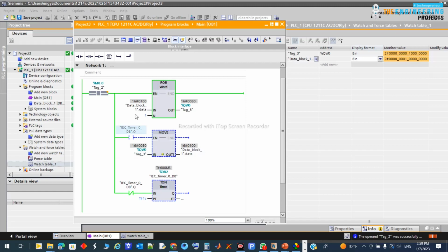After moving into the output, we update the data again and shift again, and so on, shifting, rotating, and once we reach the last bit of the output, we continue rotating the shift to the right to enable the first and the second, and so on. So again, this is a sequencer, and I also showed you how to track this data by creating a data table to show the data block I used as a mask to control your output in sequence, and also to show the output bit by bit, which is implemented.